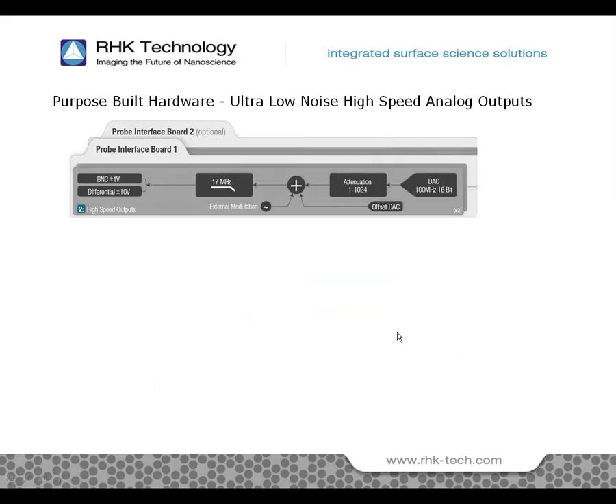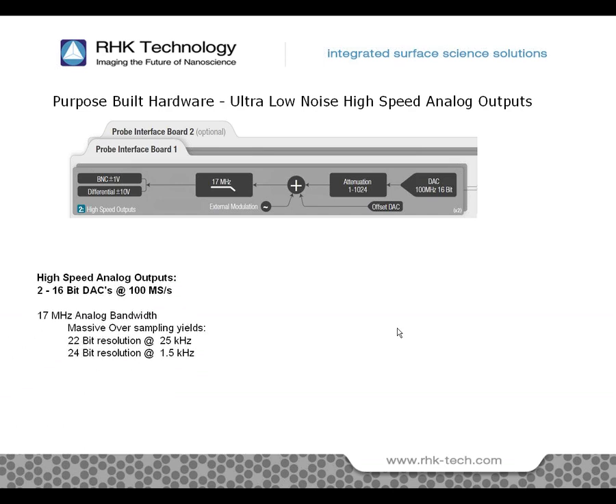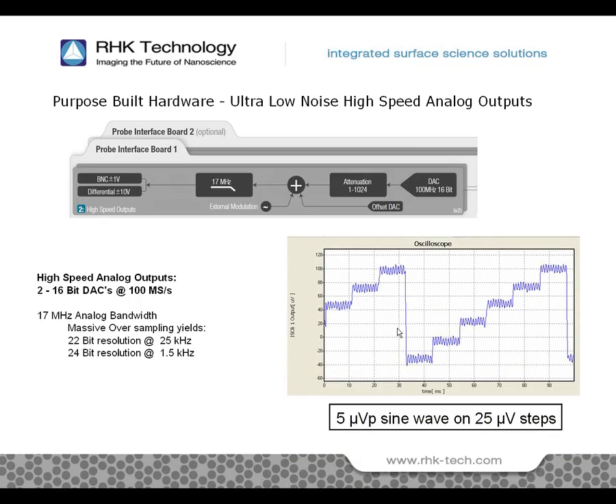Complementing the two ultra-high-speed input channels are two ultra-high-speed output channels. These outputs are typically used for the bias voltage in STM and the probe drive for AFM. The oversampling in the outputs again provides an amazing dynamic range. The output can range continuously from microvolts to volts and from DC to 20 megahertz.